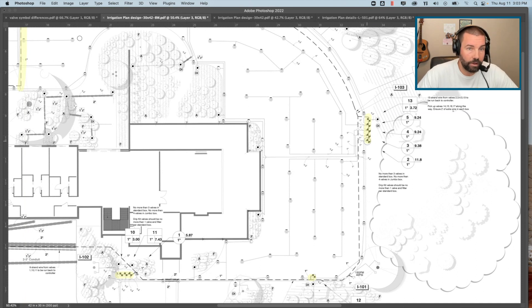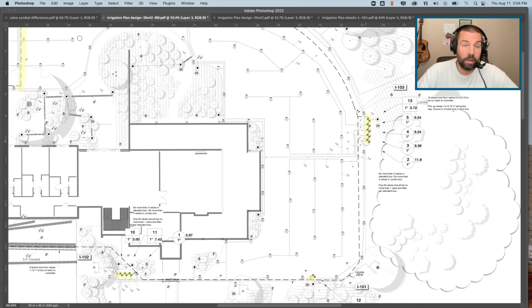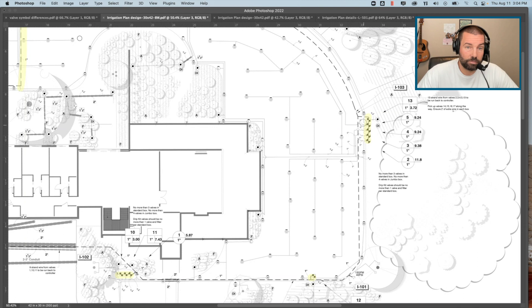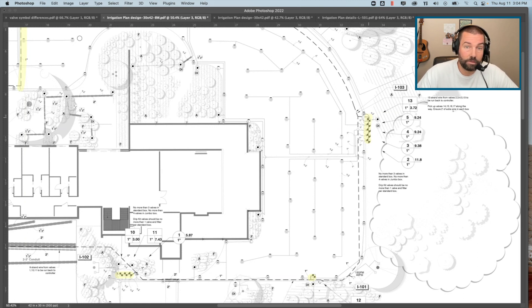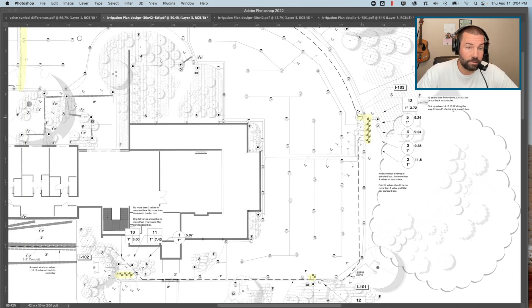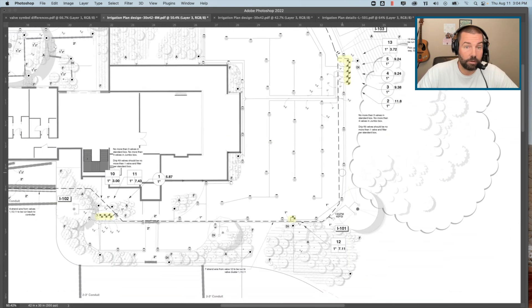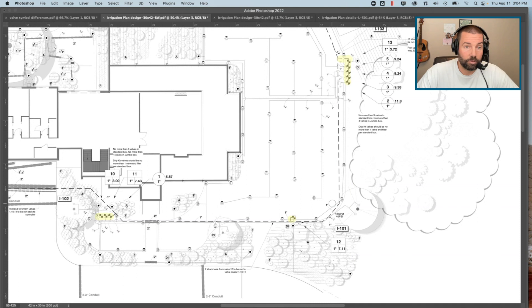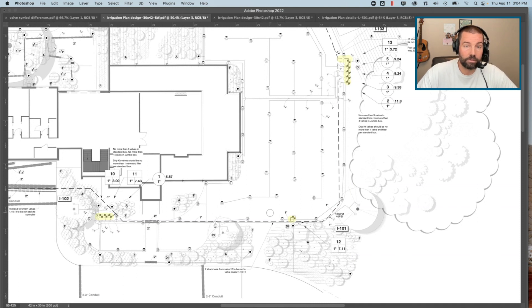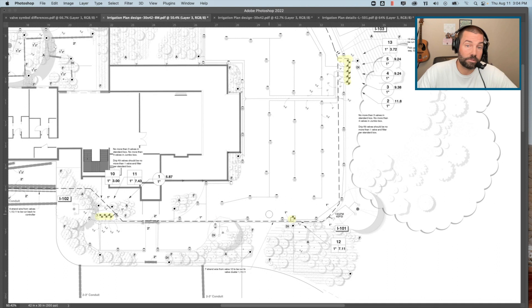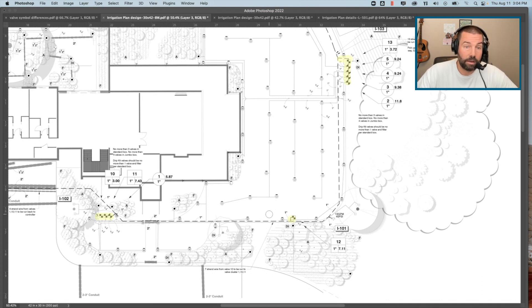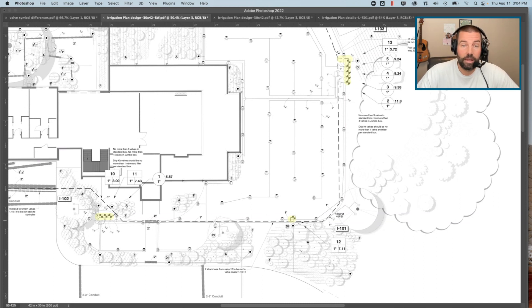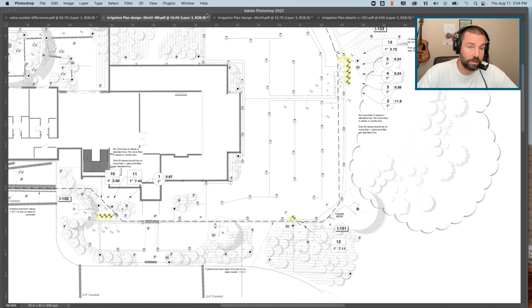Other things to think about is when we're grouping those valves together, creating those manifolds, how we place those valves appropriately so they are close to those areas and really spacing on those valves along the mainline to reduce that pressure loss in a system. Make sure that as you're placing those valves in an area where they're safe from site use conditions but still accessible for maintenance purposes.